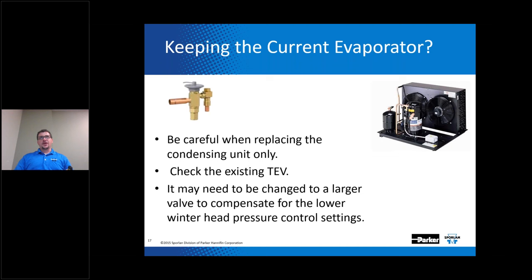I want to be clear that I'm not saying the new AWEF condensing units have improper head pressure control. The point is that the lower head pressure results in getting less capacity out of your existing TEVs, and at some point, if the head pressure falls too low due to improper head pressure control, you won't feed enough refrigerant into your evaporators — that's the bottom line.